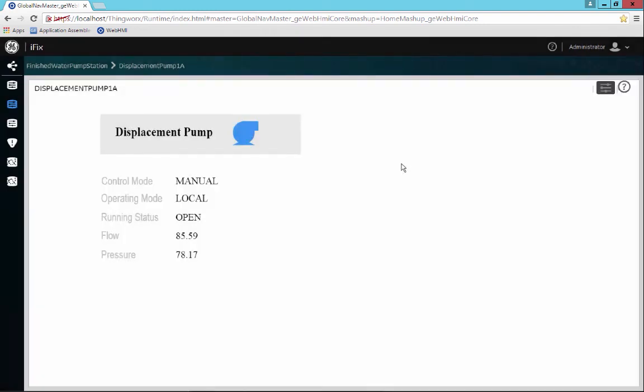If we have other grouped items inside of this control view that aren't writable, or the user doesn't have permissions to interact with that data, the gear icon would not be present — it would be hidden. They would not see it so that they could control that value, so we provide security through the set point values.